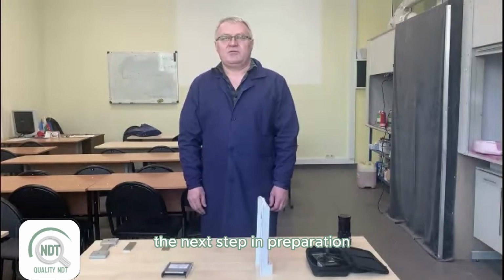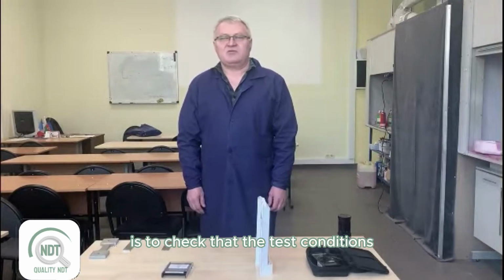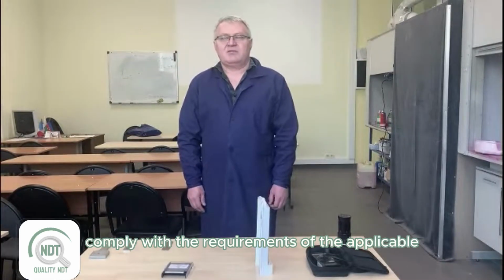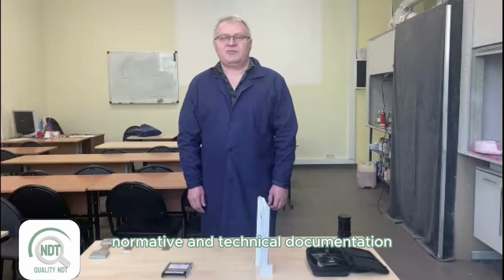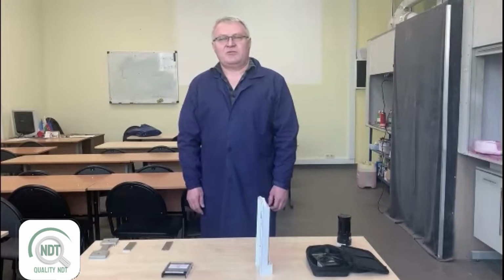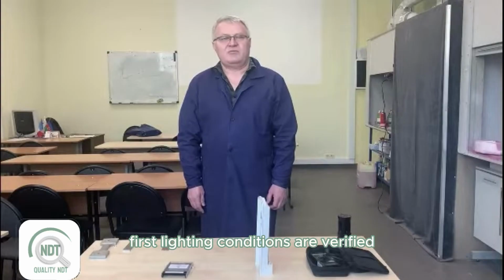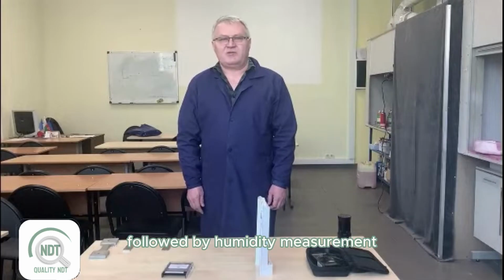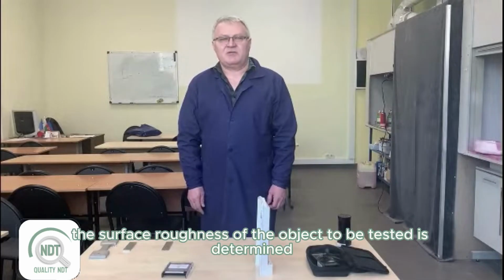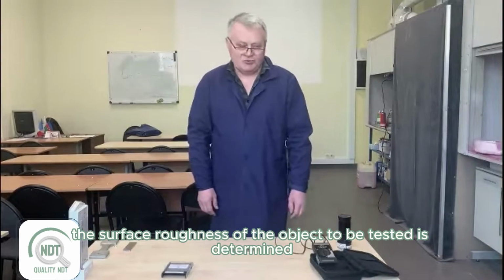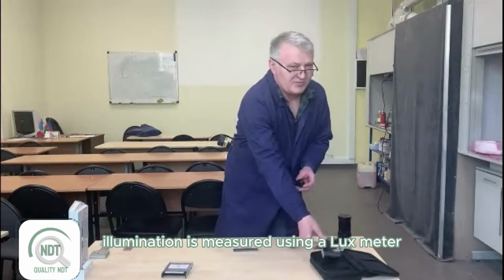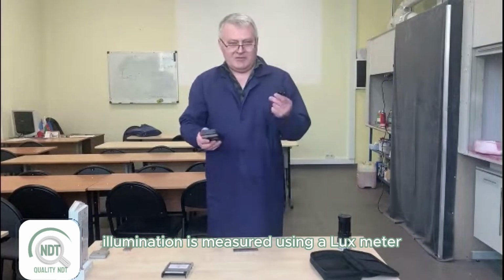The next step in preparation is to check that the test conditions comply with the requirements of the applicable normative and technical documentation. First, lighting conditions are verified. Then, temperature is measured, followed by humidity measurement, and finally, the surface roughness of the object to be tested is determined. Illumination is measured using a lux meter.